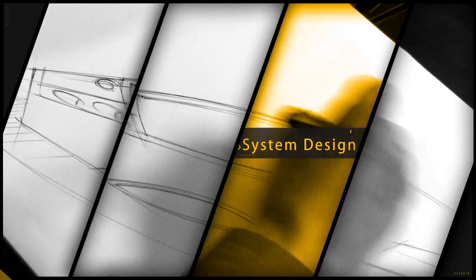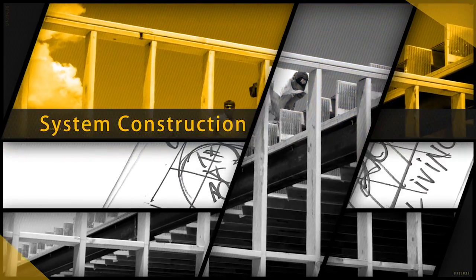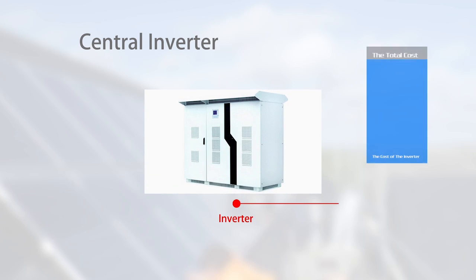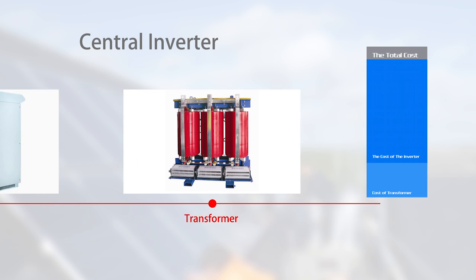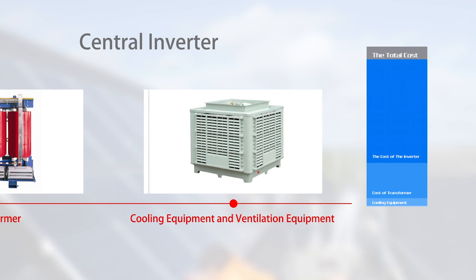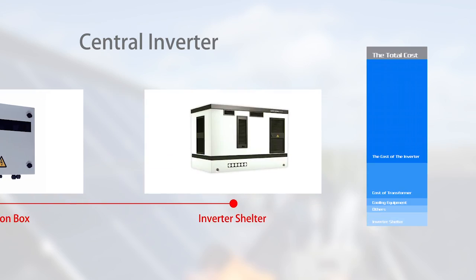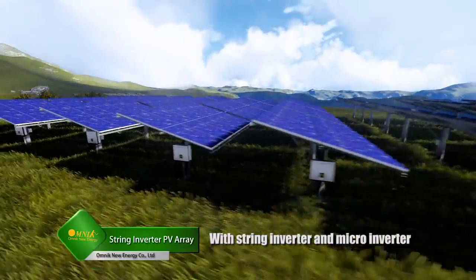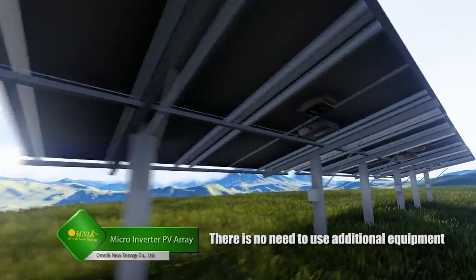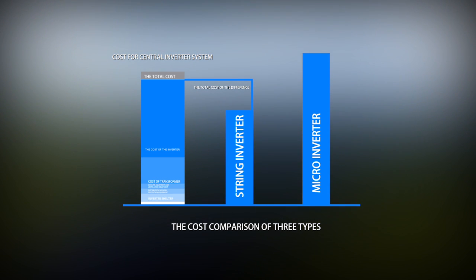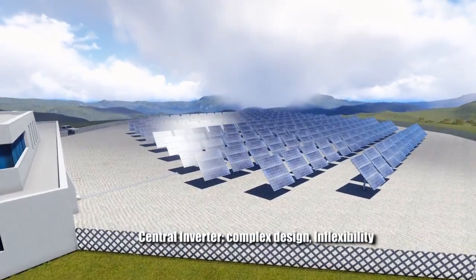To select the right inverter and maximize investment return, we will guide you from the very beginning of power plant design to later operation. Regarding system total cost analysis: if you select a central inverter, you will also need to configure transformer, cooling equipment, ventilation equipment, protection equipment, distribution box, and inverter shelter. With string inverter and micro inverter, there is no need for additional equipment. Therefore, though the upfront cost of a central inverter is cheaper, you need to pay more in additional costs than with a string inverter.